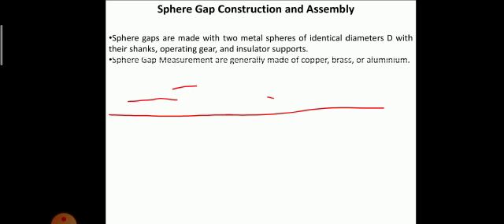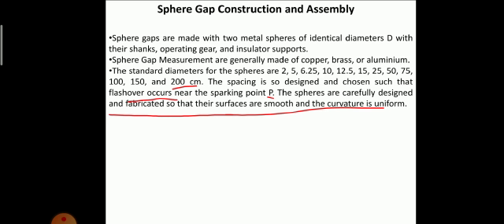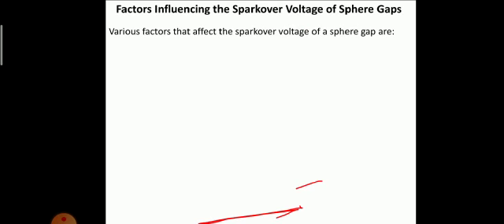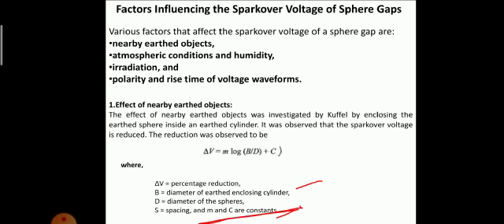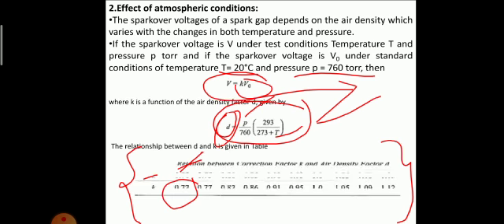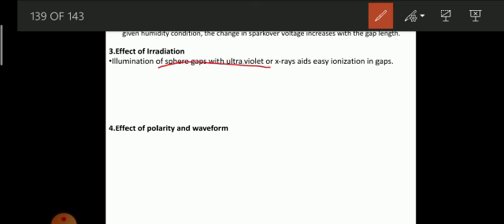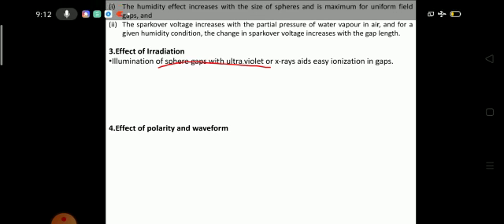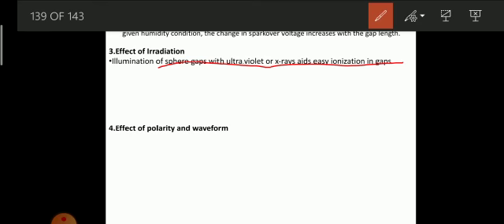But in case of irradiation, we can use UV rays or X-rays so that initially we can trigger the sphere gap, the air gap which is there between the two spheres. So it will almost ionize 20 to 30% of the air which is present between the spheres, and the rest of the work will be done by the voltage which we are supplying. So illumination of the sphere gap with ultraviolet or X-rays aids easy ionization in the gaps.